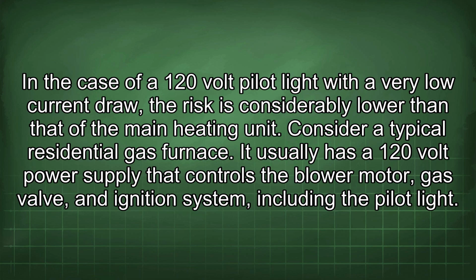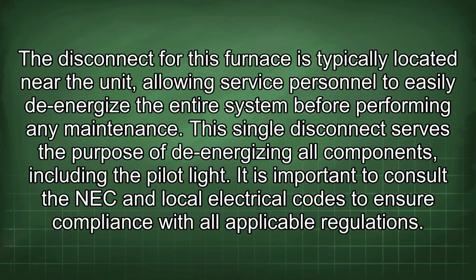Consider a typical residential gas furnace. It usually has a 120-volt power supply that controls the blower motor, gas valve, and ignition system, including the pilot light. The disconnect for this furnace is typically located near the unit, allowing service personnel to easily de-energize the entire system before performing any maintenance. This single disconnect serves the purpose of de-energizing all components, including the pilot light.